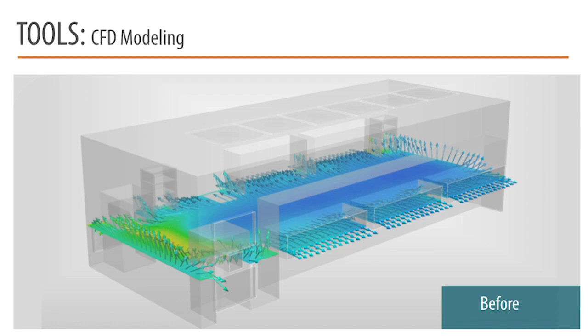Real quick example here, this is a bay from a cleanroom. You can see we've got a half dozen 4x4 fan filter units, HEPA filters on top, pushing air down. We cut a plane through this modeling at the user level. We've got a few wet benches, big open benches in this room that are chewing up a bunch of wall space, and we were having problems with certification.